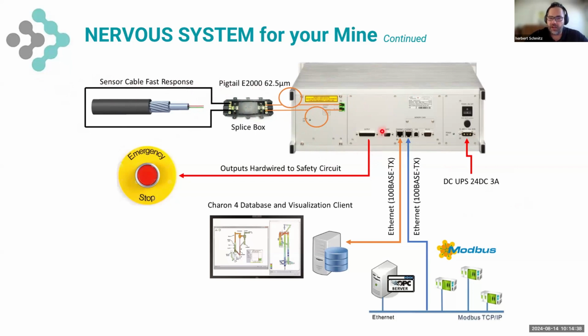We can have up to 104 digital outputs to interface with SCADA, PLC, and emergency trip circuits. A dedicated Ethernet port for our database and visualization software, a dedicated port for Modbus or industrial protocols, and very little power consumption, about 3 amps at 24 volt DC.